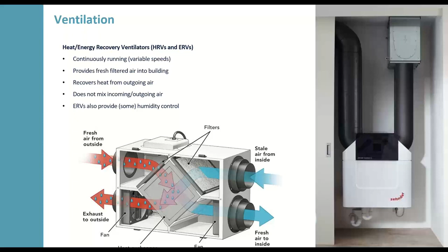Just like with heat pumps, the bigger question is not what do you use, because it's ERVs and HRVs, it's how do you install them. So this is sort of an example of the various methods that you can do. This was put together by Peterson Engineering, so I thank them for this, but you sort of see three general concepts. So there's unitized, or local, as it's sometimes called, and this is where you put one ERV in every single unit. So this is what the distillery did. Then one of these units in every single unit. So if I actually go back, this image of a Zehnder unit you can see here, this is what they had. So they had a closet in every single unit that had one of these systems inside of it.